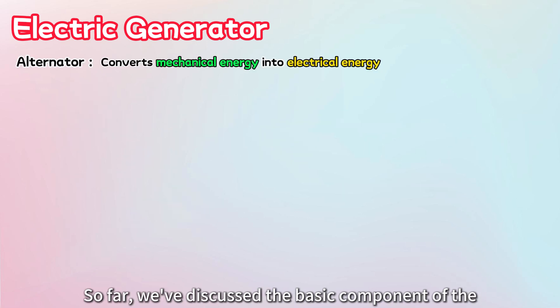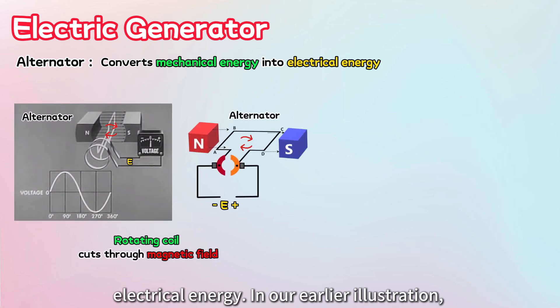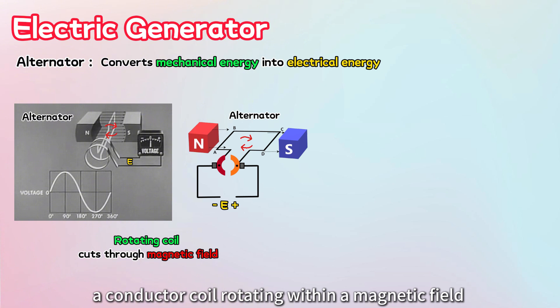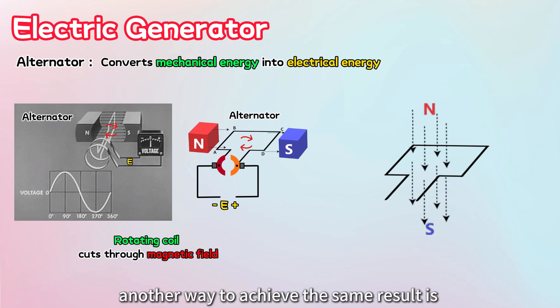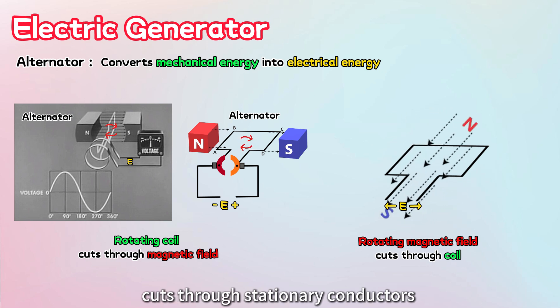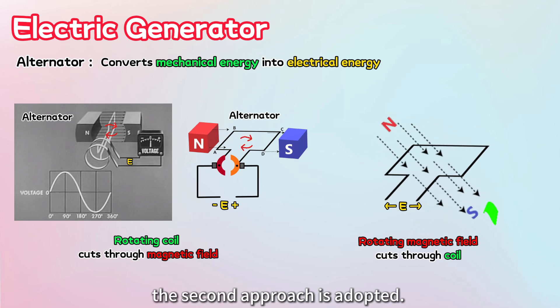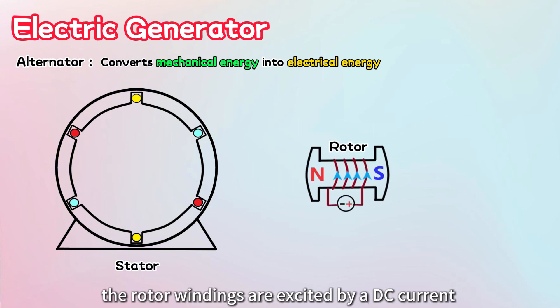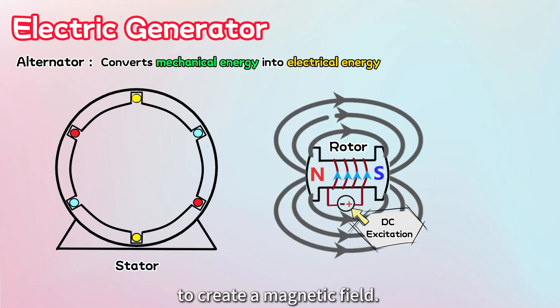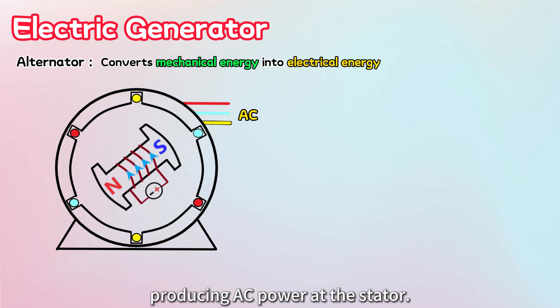So far, we've discussed the basic component of the generator, also called the alternator, which is the part that converts mechanical energy into electrical energy. A conductor coil rotating within a magnetic field can generate EMF. But instead of rotating the coil, another way to achieve the same result is by creating a rotating magnetic field that cuts through stationary conductors to generate electricity. In real-world generators, this second approach is adopted. The stator, or stationary part, holds the stator windings. The rotor windings are excited by a DC current to create a magnetic field. When the rotor spins, the magnetic field rotates and cuts through the stator windings, producing AC power at the stator.